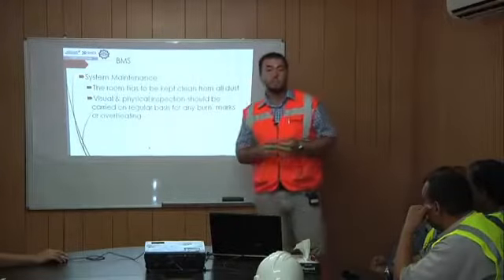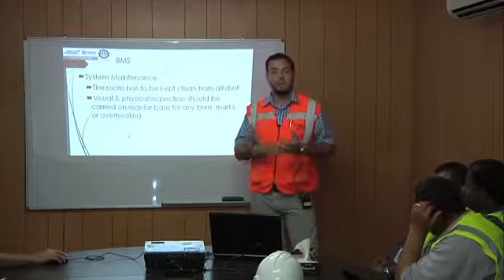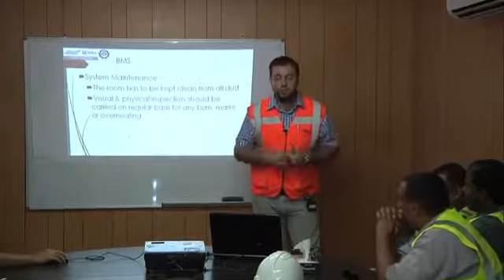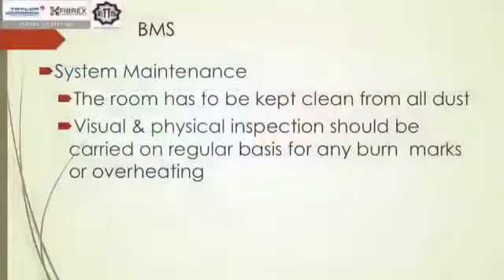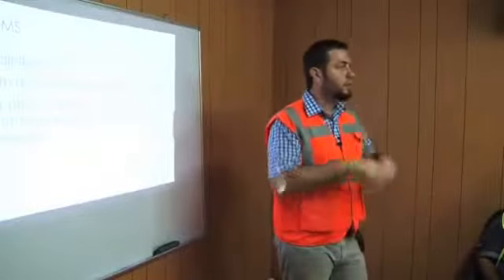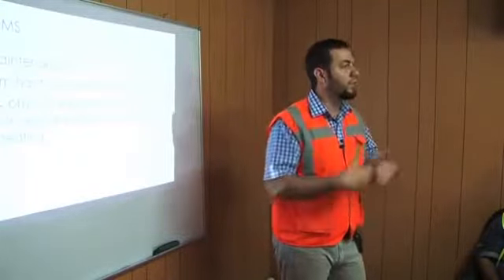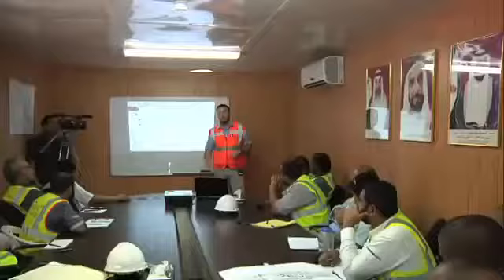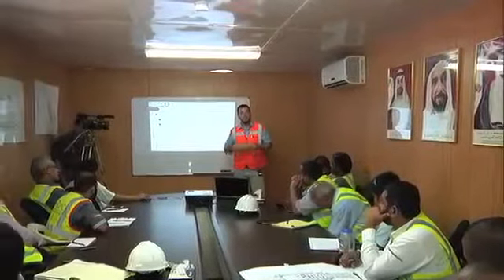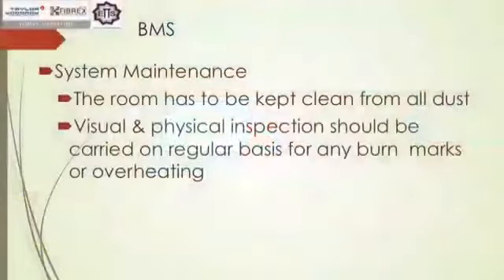To maintain, the room obviously has to be clean. You've got a computer sitting there. You don't want dust to go inside. You don't want it to shut down. All your DDC panels are located in closed rooms, except the 2 that are located outside. These outside panels are IP65. They're fully sealed, waterproof. So the only issue is that once you open it, just to check it out, make sure that you close the DDC panel, you close the cover properly, you seal it properly, and not leave it open for dust or anything to go inside.